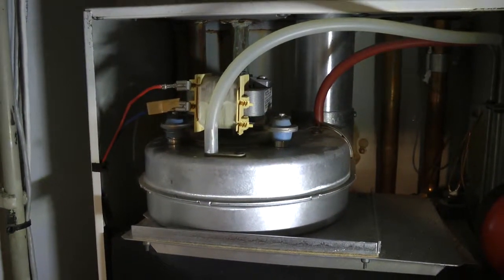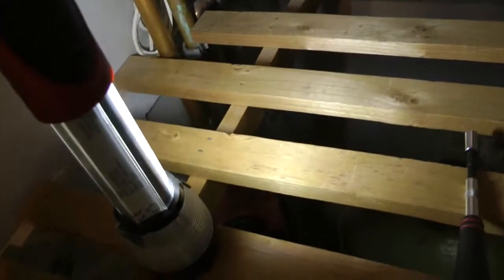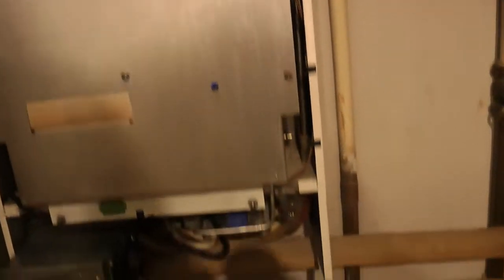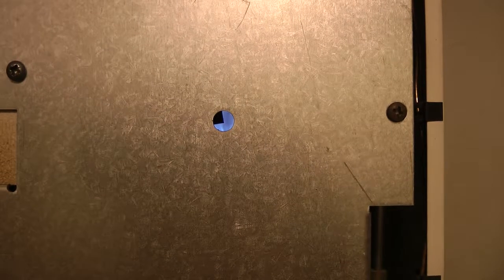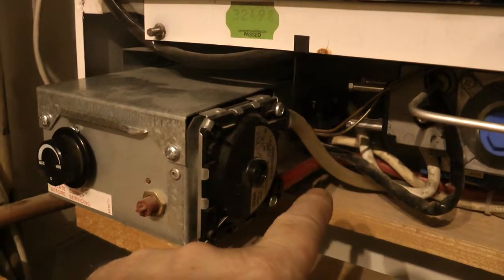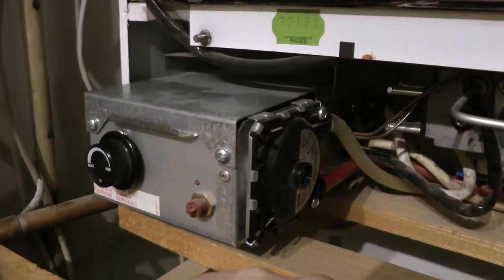All right. That's it. Fixed. Well, apart from dropping me torch. Well, that's cool. Yeah, looks like a nice blue flame in there. So, it's being delivered the right amount of oxygen. And just there, you can see the two pipes coming down from the motor cowling into this unit here, which has got an O2 sensor in it. Like I said before, if that fan doesn't run, the boiler won't start.